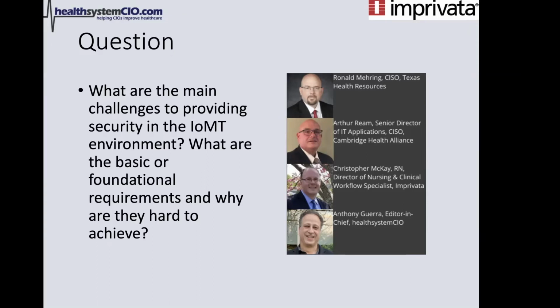It's very complicated, maintaining that balance of safety and privacy, which is what the security controls are really trying to do in the middle of all that. So it becomes very complicated. The table stakes, the foundation of this, from my perspective, is controlling access to the device, which from a network perspective is controlling data flow, and ensuring that we can effectively monitor for anomalies around those devices. In other words, is something bad happening, or are they operating normally? So those two things are the foundational aspects of what we're trying to do within that environment, and some of the issues with that, the complexity with that.